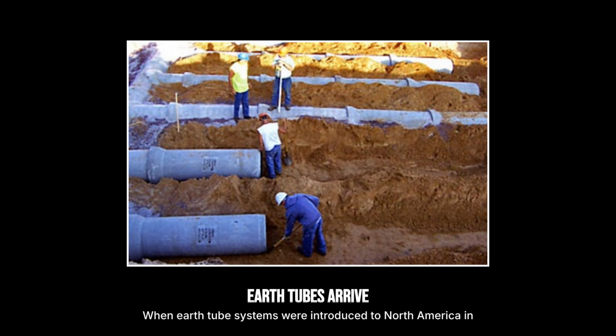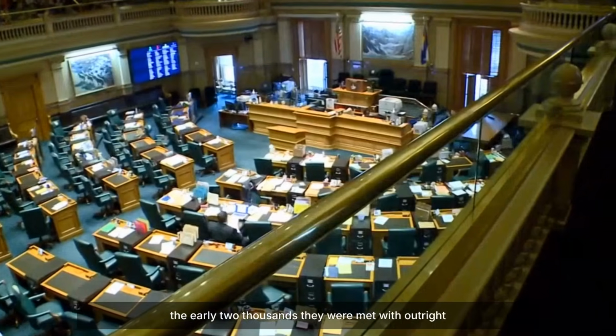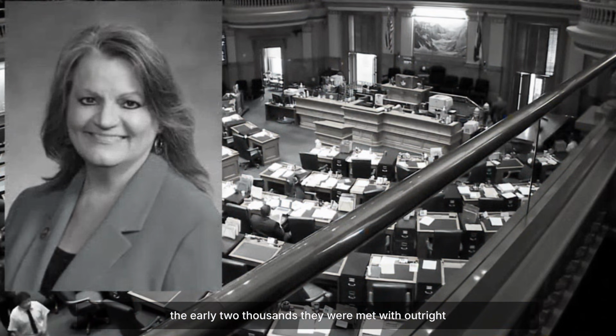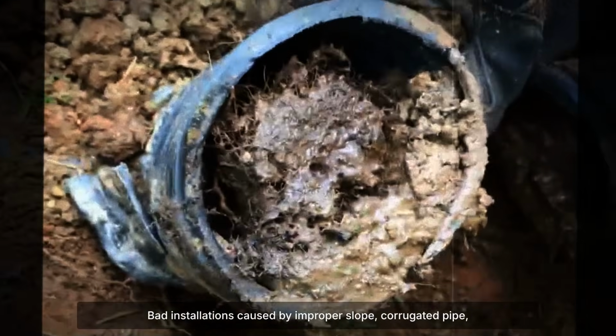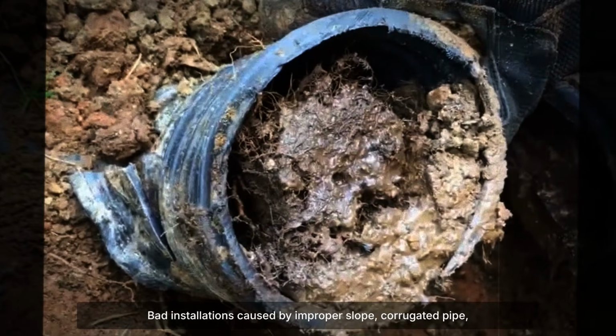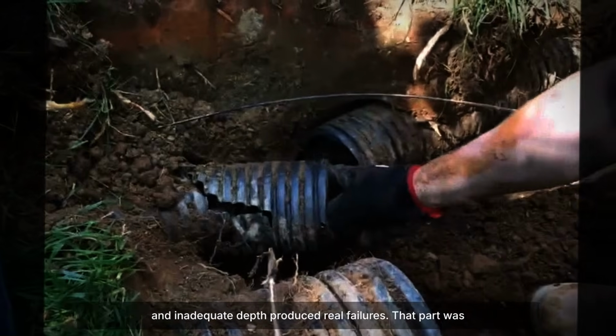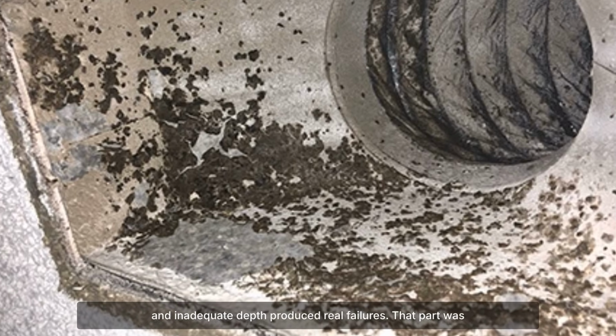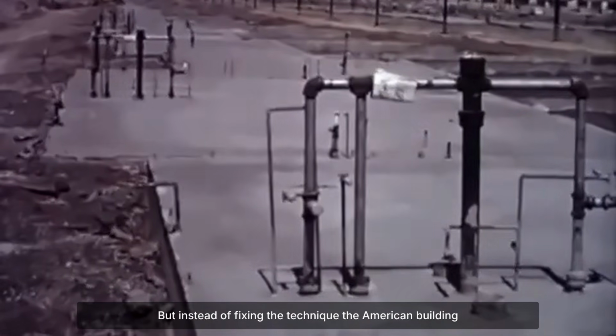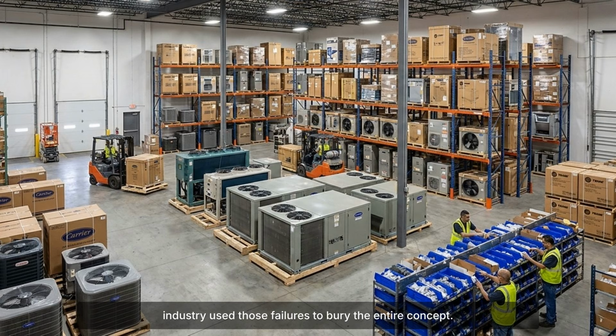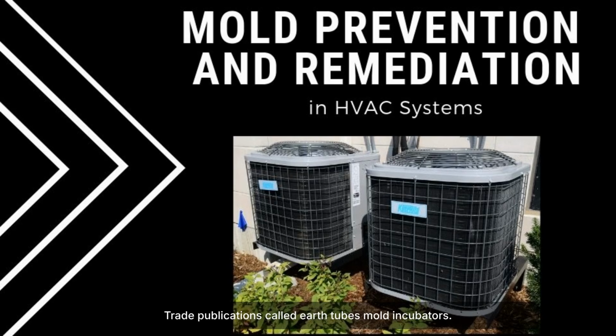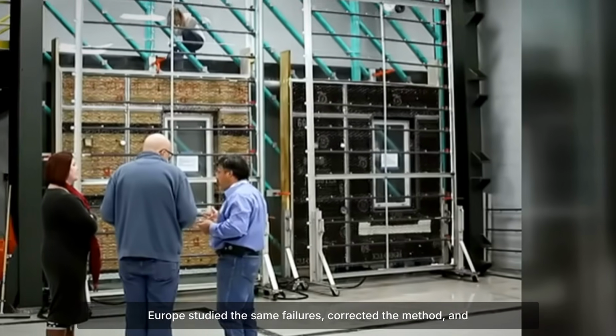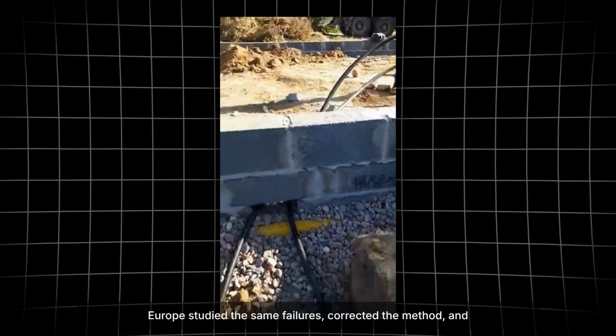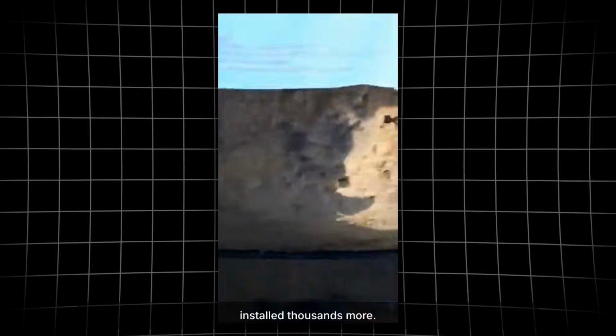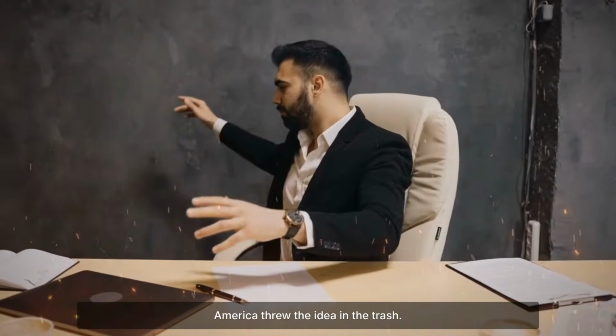When earth tube systems were introduced to North America in the early 2000s, they were met with outright hostility. Bad installations caused by improper slope, corrugated pipe, and inadequate depth produced real failures. That part was true. But instead of fixing the technique, the American building industry used those failures to bury the entire concept. Trade publications called earth tubes mold incubators. Europe studied the same failures, corrected the method, and installed thousands more. America threw the idea in the trash.